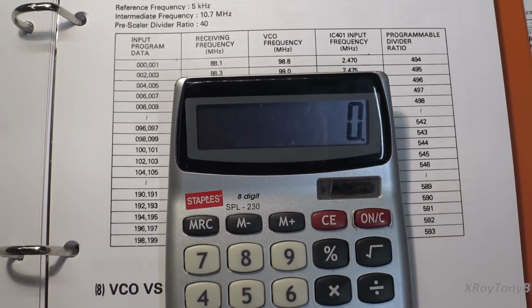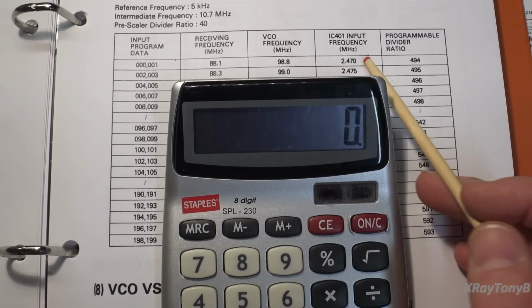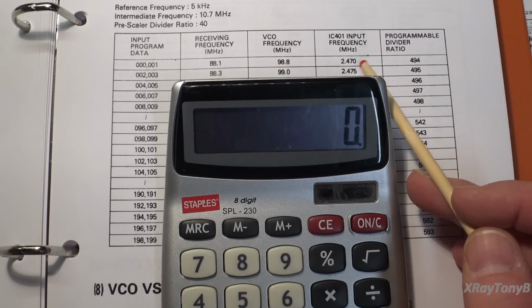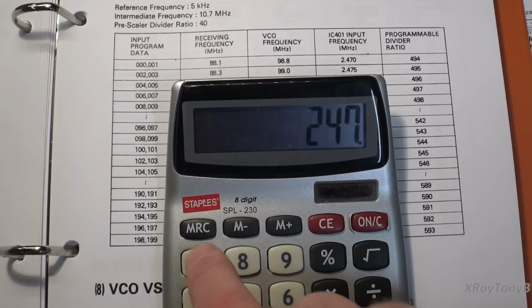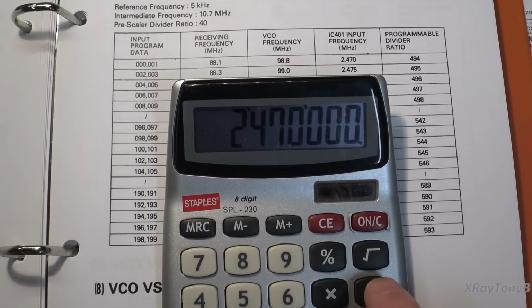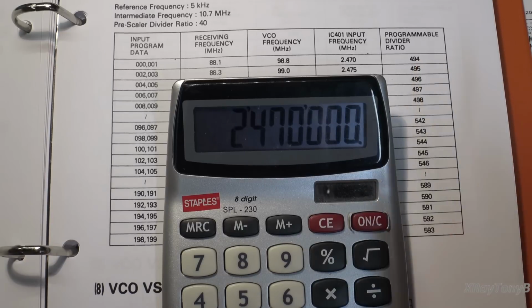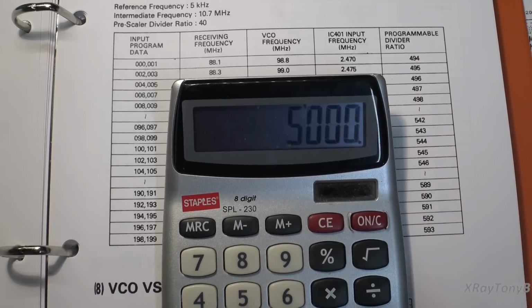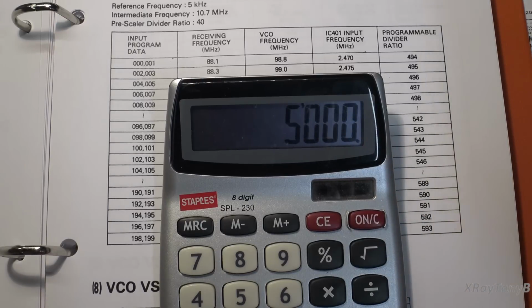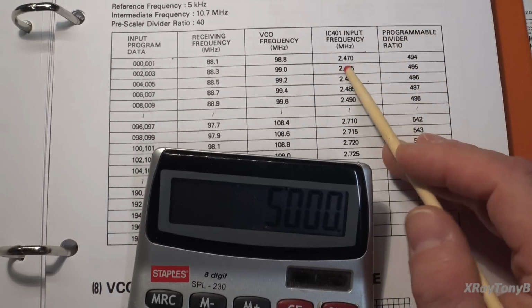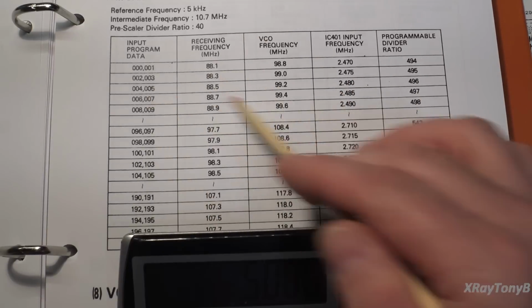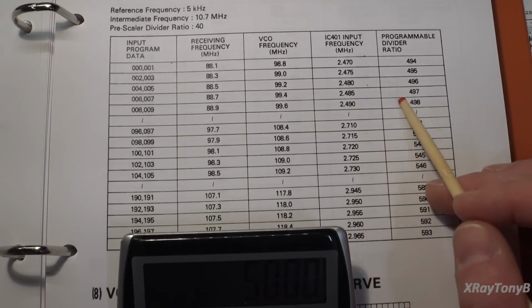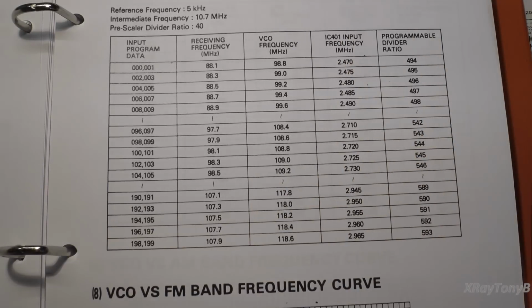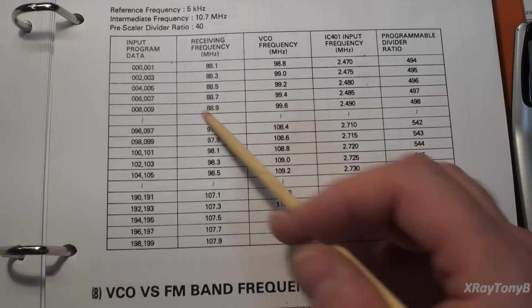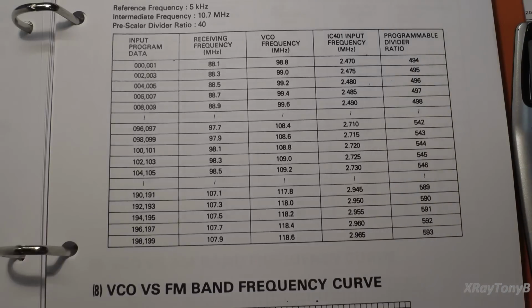So just to give you an example, if that frequency is 2.47 megahertz, that would be 2,470,000 hertz divided by that divider ratio, 494. You get 5,000, or 5 kilohertz. I'm sorry, I was saying megahertz. It's 5 kilohertz, and 10 kilohertz, if you remember. And you can see if we go down the line and divide these two numbers all the way down, depending on the frequency, these two numbers will always come out to 5 kilohertz. So that's a mathematical way of measuring these frequencies and making sure they're correct.